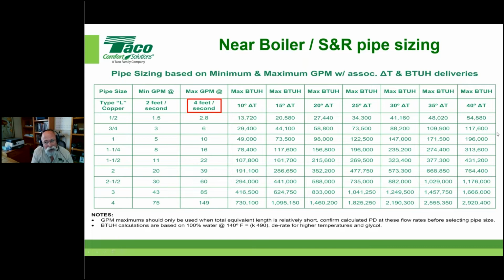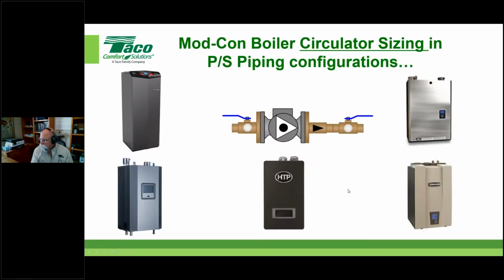I could do 200,000 BTUs. Now you might not want to do that, or you might, depending on how good you feel about what's written in the boiler's manual, etc. I'll refer you back to that every time. In reality, it's impossible to oversize a header within reason. So if the flow rate says 1 inch and you want to put 1.5 inches, it's only going to be of benefit to you. It won't hurt you much. The only thing to remember is that we want to keep our velocity at 2 feet per second or slightly higher for the bubbles and so on.